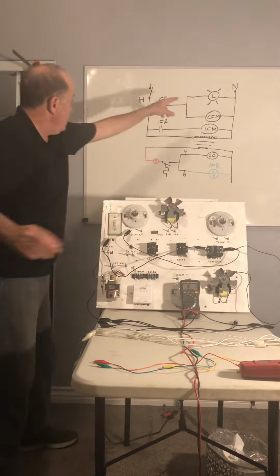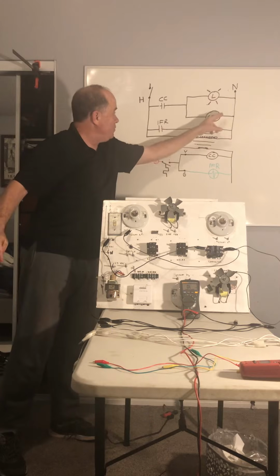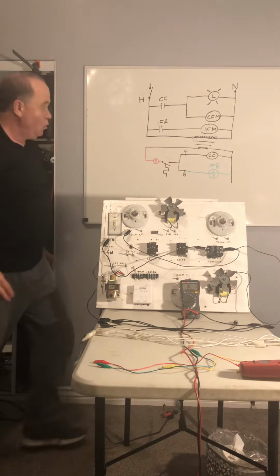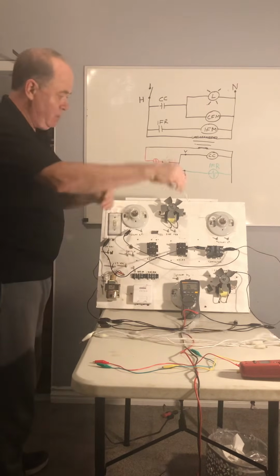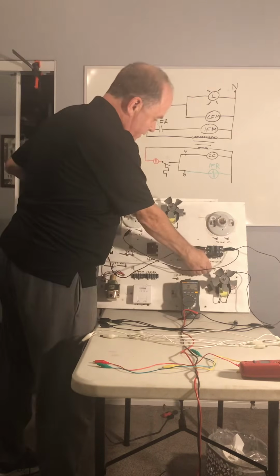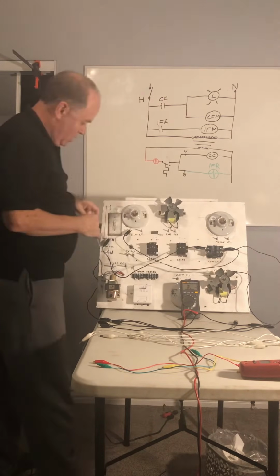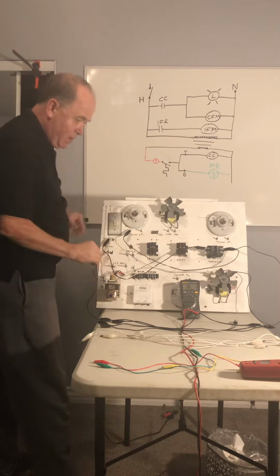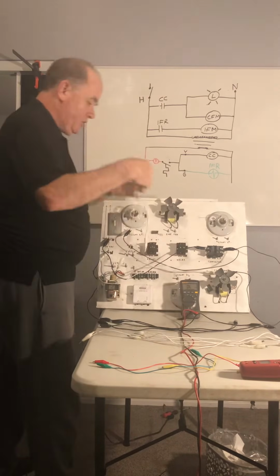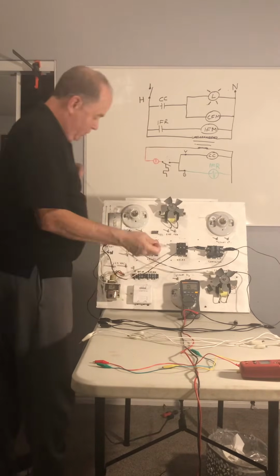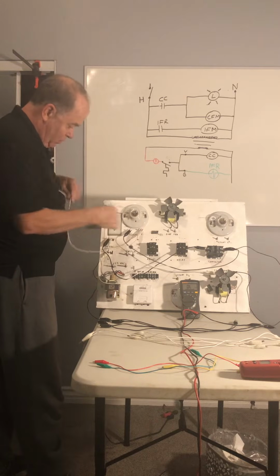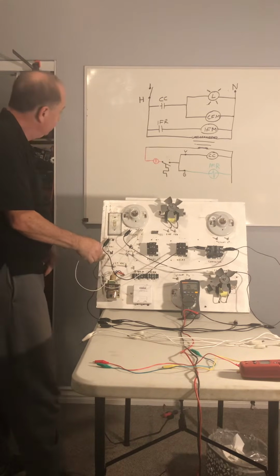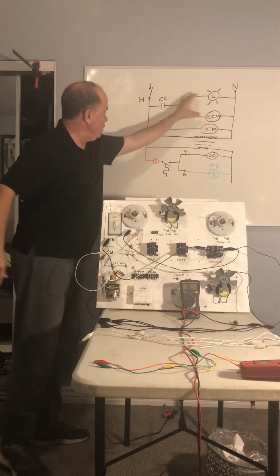And then off of the light, we go back to neutral and back to neutral with the condenser fan motor. Let's do that now. The condenser fan motor here goes back to neutral. And the light, also we're using white for neutral, goes back to neutral. That completes this portion of the circuit.